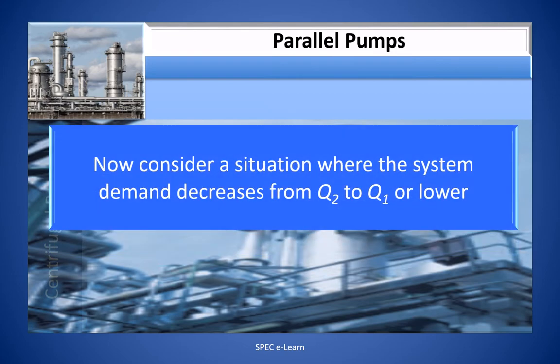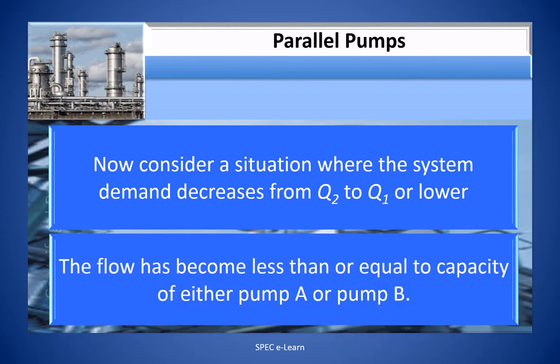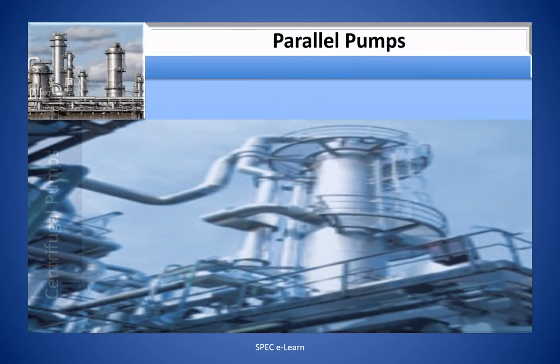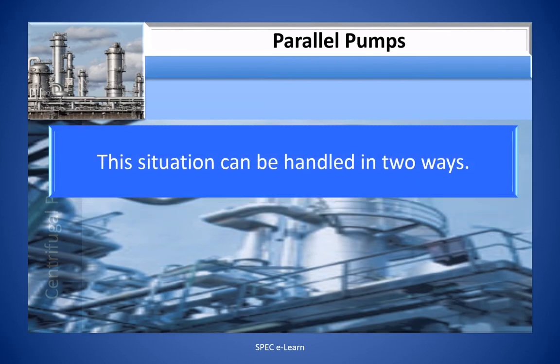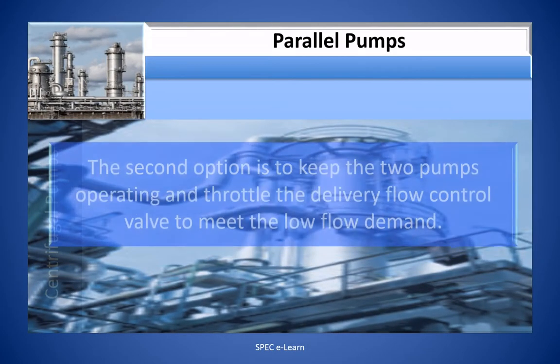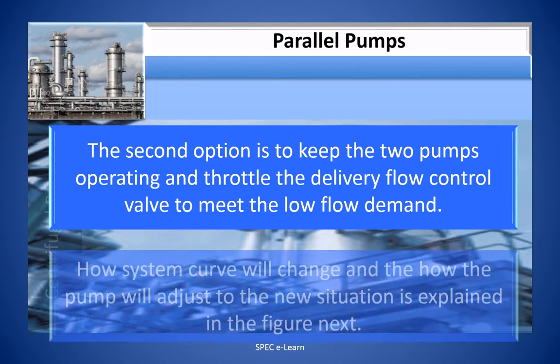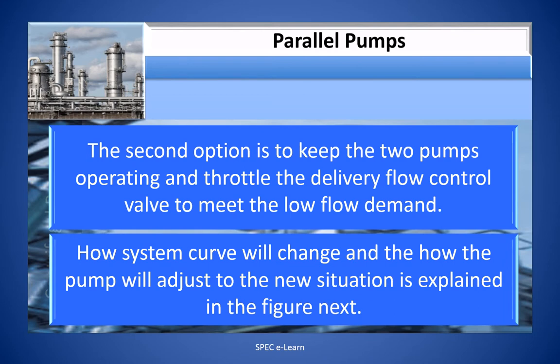Now consider a situation where the system demand decreases from Q2 to Q1 or lower. The flow has become less than or equal to the capacity of either pump A or pump B. The situation can be handled in two ways. One option is to stop one of the pumps and continue to meet the system demand of Q1 with the other pump. The second option is to keep the two pumps operating and throttle the delivery flow control valve to meet the low flow demand. How the system curve will change and how the pump will adjust to the new situation is explained in the figure next.